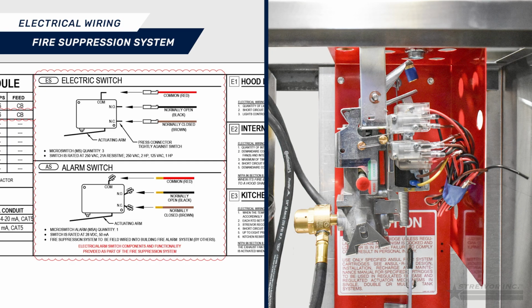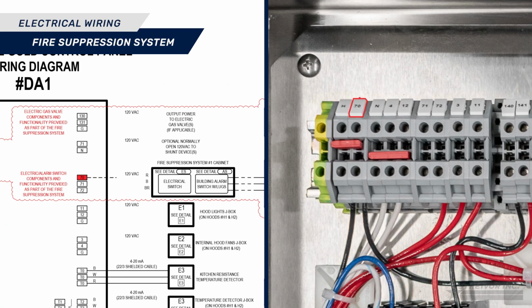To begin wiring, locate an FSS electrical switch located in the FSS control head. Wire terminal block 70 to the common leg of the FSS electrical switch. Wire terminal block 71 to the normally open leg of the FSS electrical switch. Wire terminal block 72 to the normally closed leg of the FSS electrical switch.